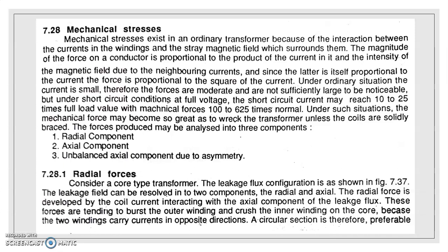solidly braced. So the forces exerted on the transformer are analyzed with three components. First is the radial component, second is the axial component, and third is the unbalanced axial component due to asymmetry. Let's see the radial forces one by one.